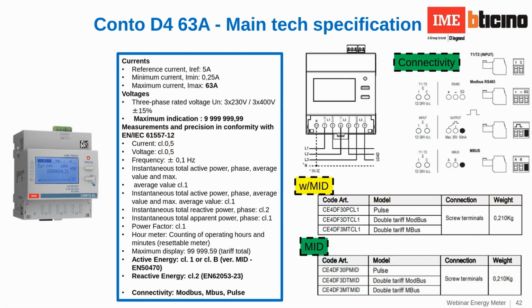Okay, now we have a look at the three-phase. Here you see, so basically the Conto D4 with direct insertion, as I said, up to 63 ampere. The technical parameters are the same as the Conto D2, but in 3-phase clearly. All voltage connectors are on the bottom side for an easy installation. In the upper part, you find the connector for external connectivity, like in the Conto D2 that was explained before. And these connectors are detachable, meaning that an electrician can connect the bus without the energy meter directly installed on the bus.